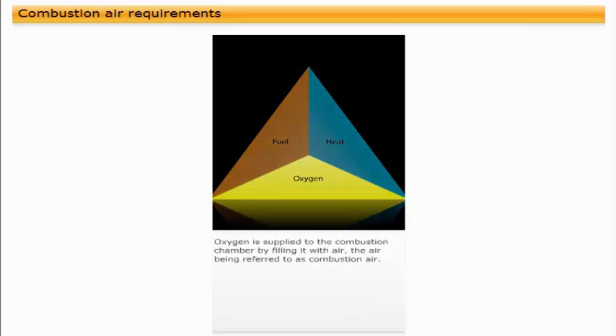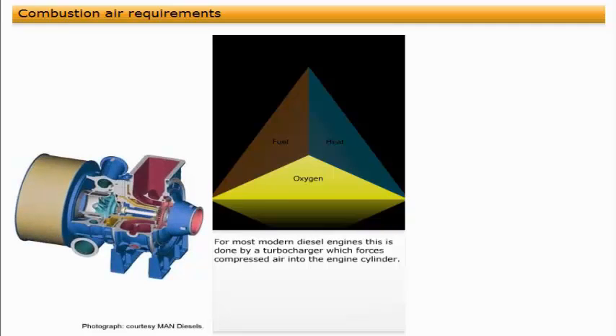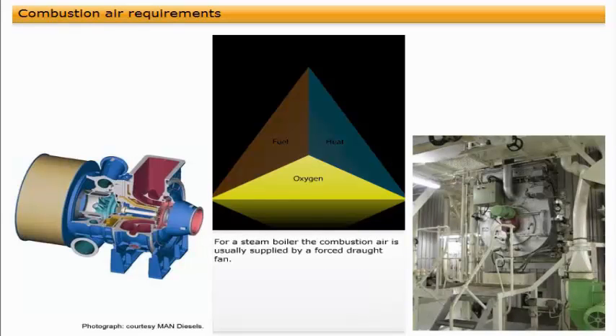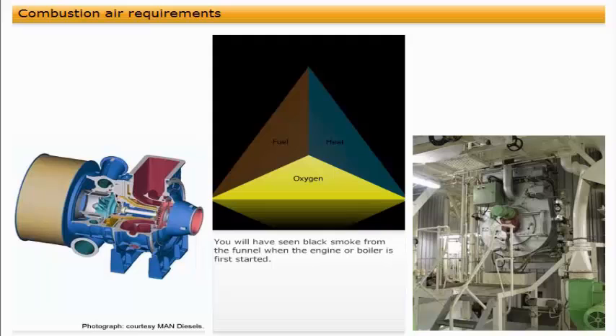To allow combustion of fuel to take place, there must be oxygen present. Oxygen is supplied to the combustion chamber by filling it with air, the air being referred to as combustion air. For most modern diesel engines, this is done by a turbocharger, which forces compressed air into the engine cylinder. For a steam boiler, the combustion air is usually supplied by a forced draft fan. The amount of air supplied, along with other requirements, will dictate how good the combustion will be.